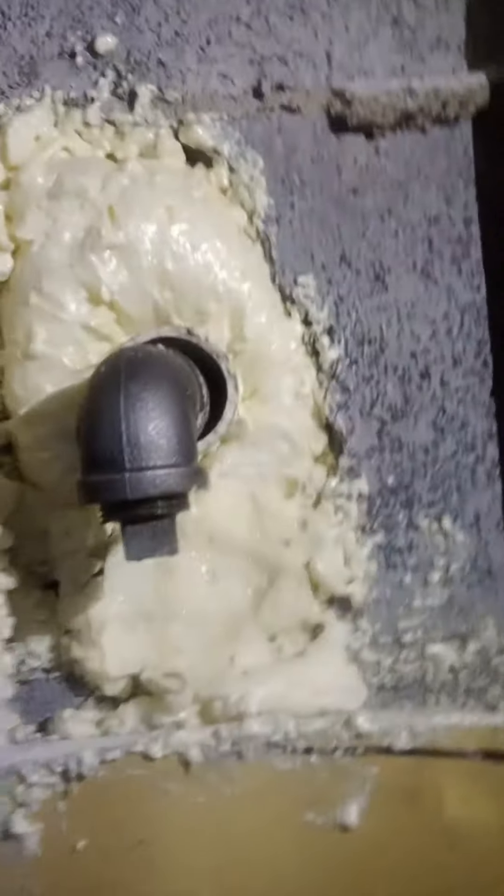The sleeve, by code, can only be on the outside. Since we don't know the condition of the appliance, I removed the valves and everything is being capped — capped right there and capped right here.